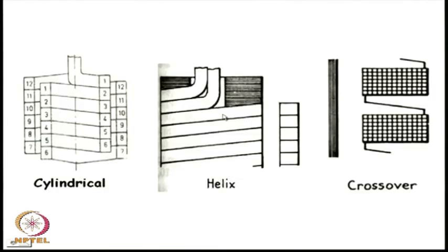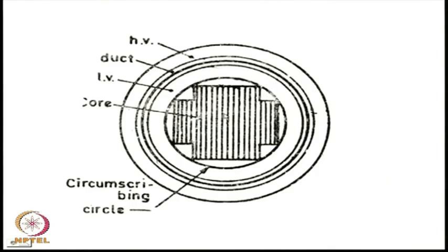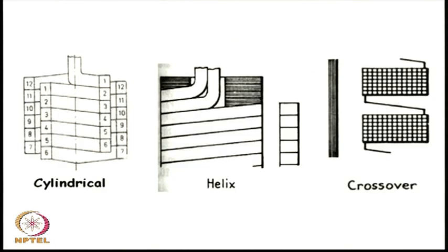The next important thing in transformer construction are the windings. The purpose of the windings are to carry the magnetization current that produces flux and also transfer power from one winding to another. These windings are made up of solid or stranded copper or aluminum strips. There are different types of windings that are used. It depends on the power and the voltage rating of a particular winding.